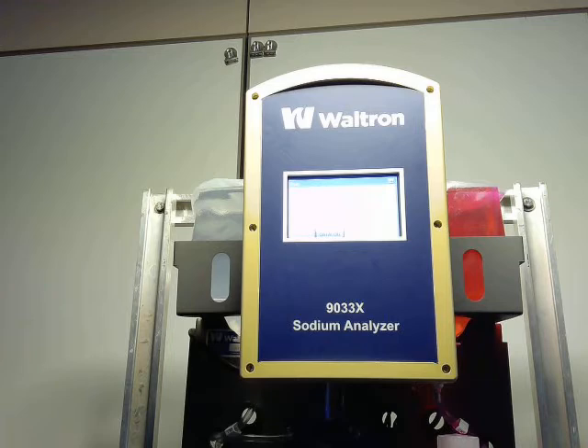Typically, if we fail on the high side above 110, usually that's a reference electrode issue. A lot of times it's just the KCl solution inside the electrode that's not flowing properly through the electrode tip. Most of the time the reference electrode issue has to do with that solution. You can empty the solution out of that probe, flush the whole probe out with DI water, rinse it back out with KCl solution, and put it back in service. About 9 times out of 10, your reference electrode will be back to good after flushing out that solution.